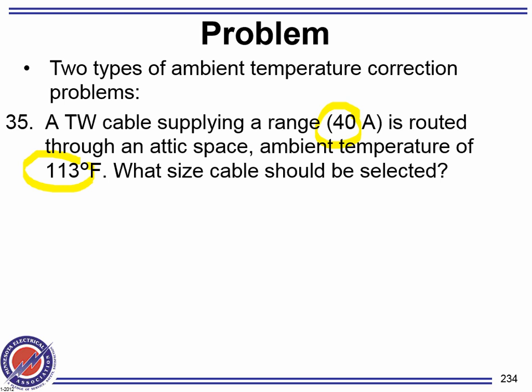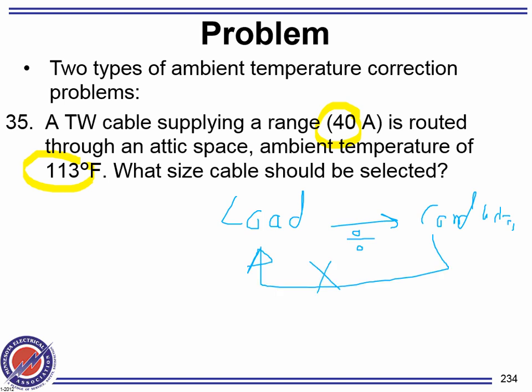Okay, so there's load and there's conductor. Here's my load, and there is the conductor. If you have the load and you need to find the conductor, you must divide by the derating factor. If you have the conductor and you need to find the load, you must multiply by the derating factor. Divide, I'm going to say D here, multiply by D. One more time.